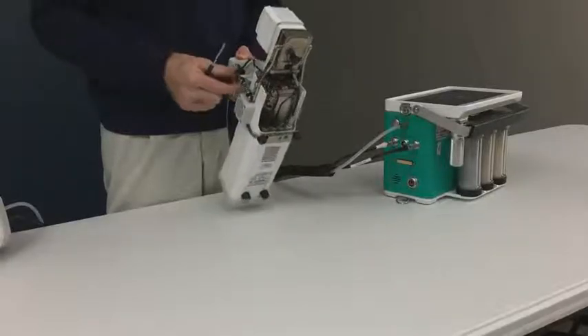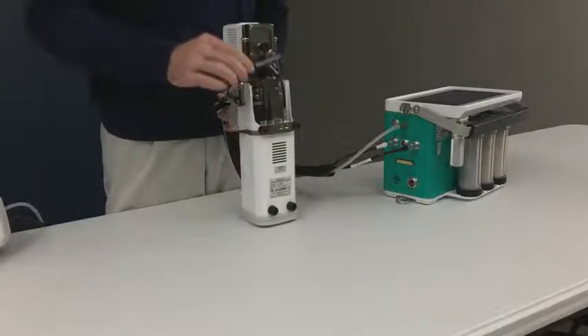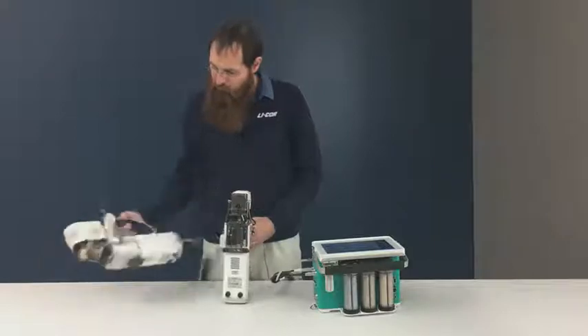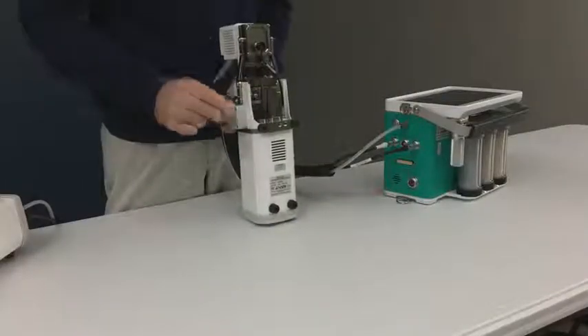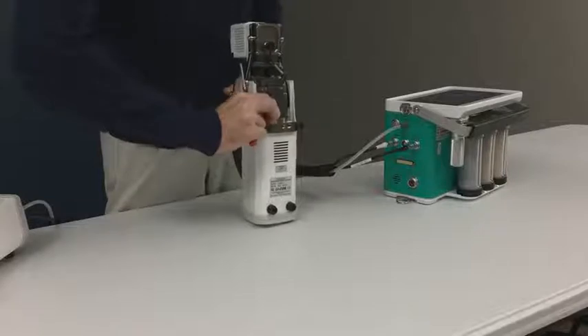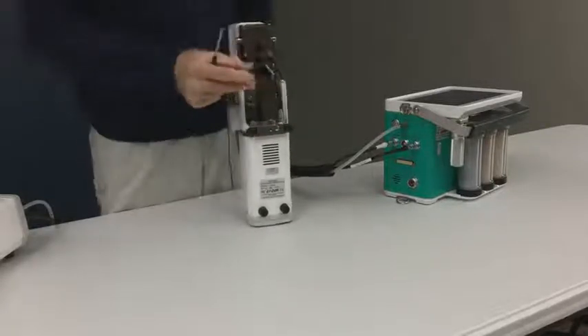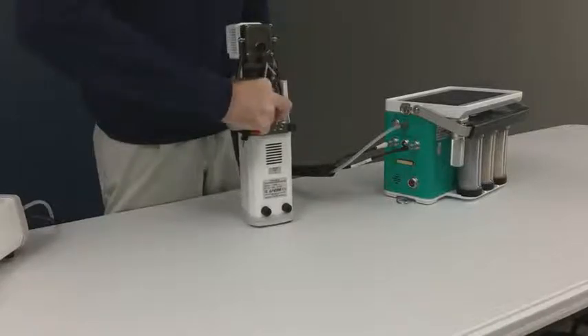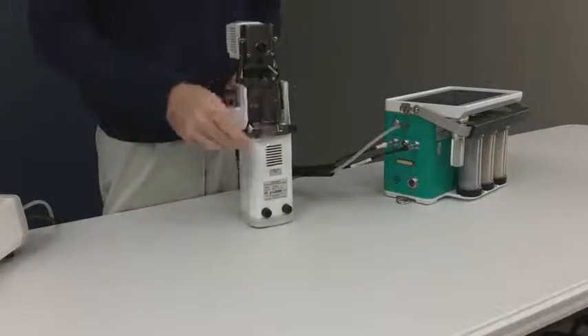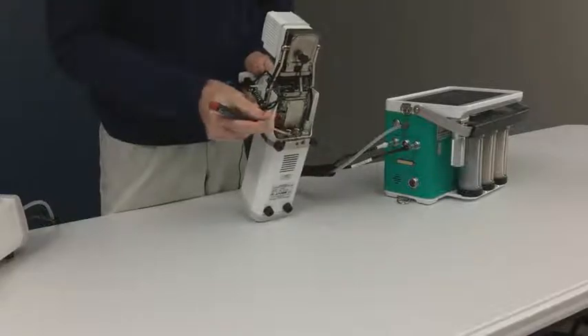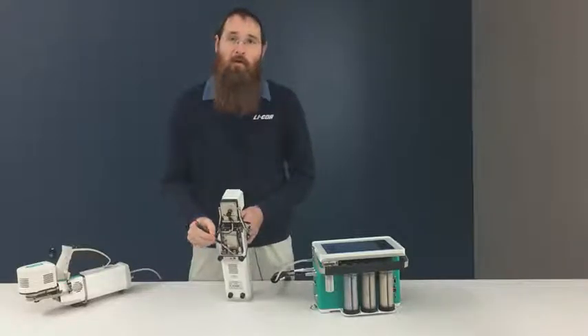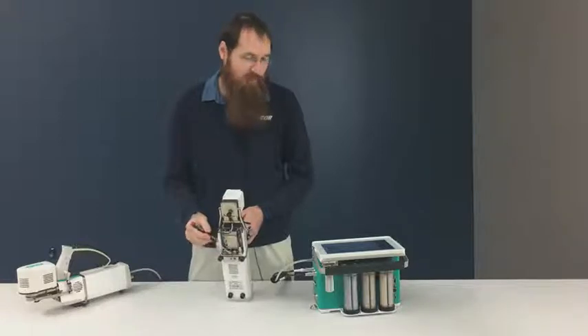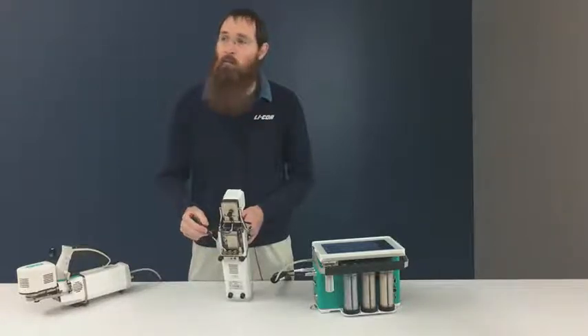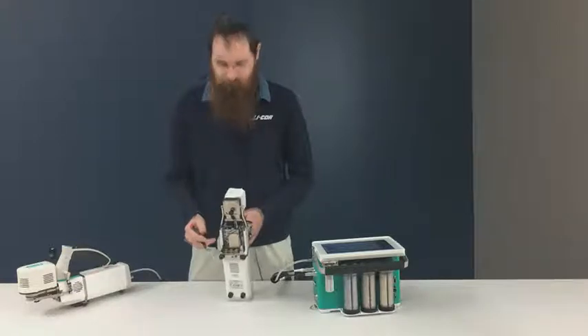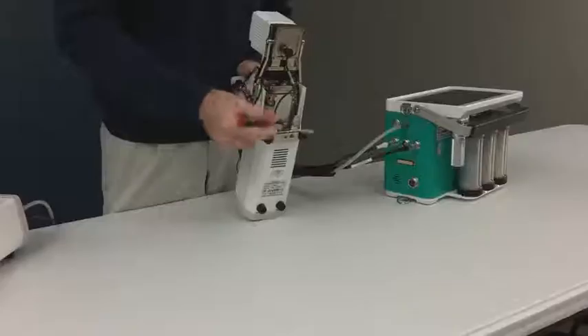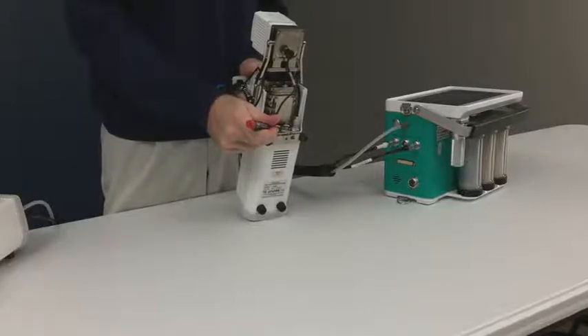There are a few connections on the bottom side of the sensor head, normally covered with a skid plate, which you can see on this chamber. These connections include one for the PAR sensor, using stereo jacks, and one for a leaf temperature thermocouple, also a stereo jack. They're labeled here, with one called T1 and one T2. The instrument supports plugging in multiple leaf temperature sensors at the same time, which I'll show in software. Then there's a port called LS, the light source connection.